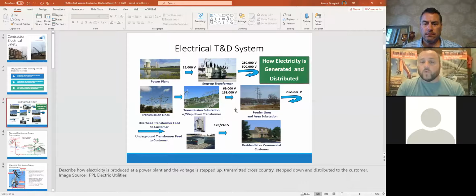And transport one more time today over what you see out there, us installing the big steel monopoles to what we call an area supply substation. And that substation, approximately 103 by 130 that you see in the residential areas. Inside of this substation, again, we have a transformer that basically takes the 69 and the 138, and we step it down to a distribution level of 12,000 volts of electricity. So 12,000 is the wooden poles that are outside of your home, 3 wires on top.